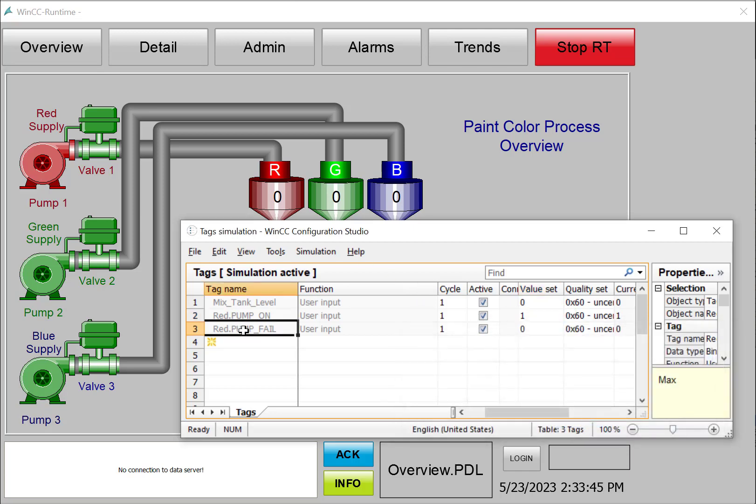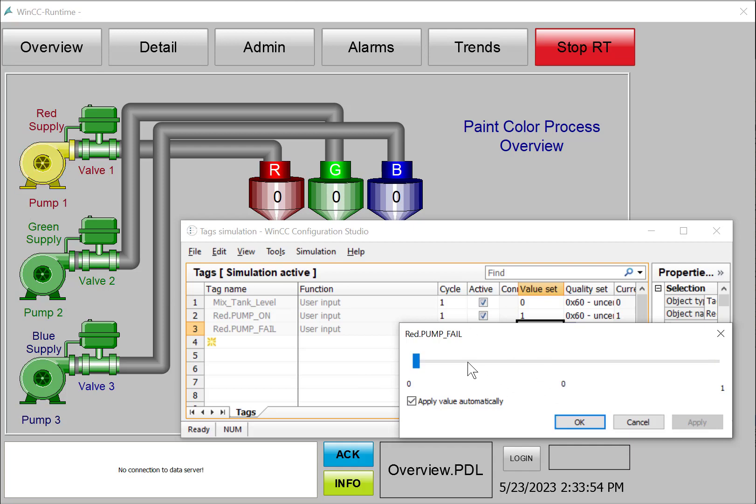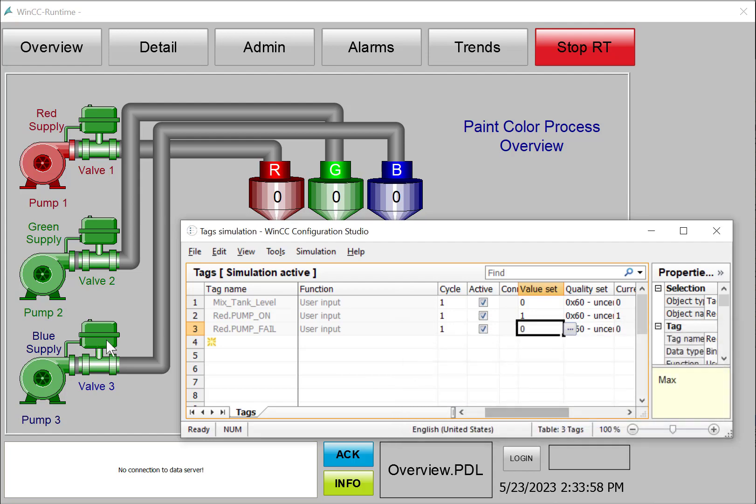And then for my red pump fail, we'll do the same thing. I'll apply that, and then you can see it showing the fail indication. If I set it back to zero, it stops doing that. So those are configured correctly.